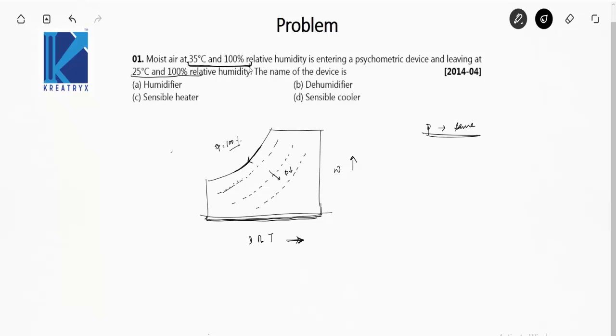The moist air enters at 35 degrees Celsius and leaves at 25 degrees Celsius. Since DBT increases in the rightward direction, we are moving in the downward-left direction along this constant relative humidity line. At 35 degrees Celsius, let the specific humidity be omega 1, and at 25 degrees Celsius, let the specific humidity be omega 2.